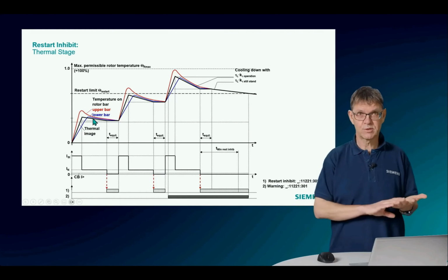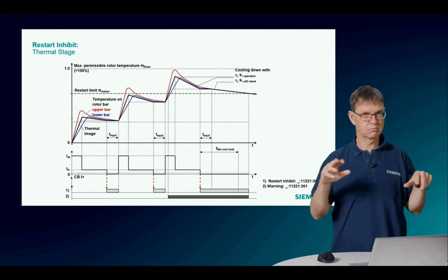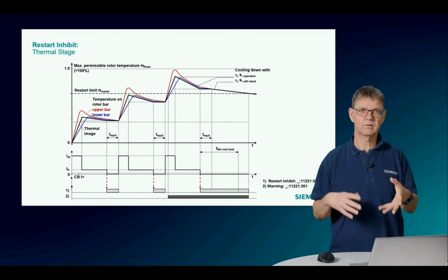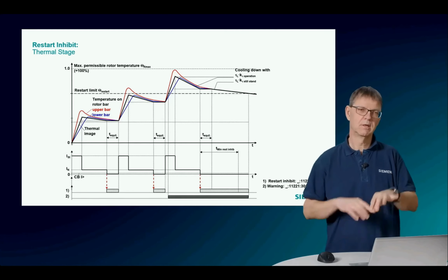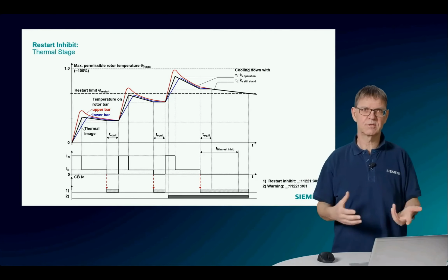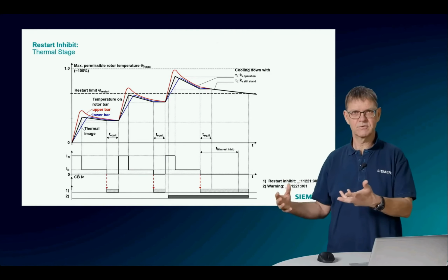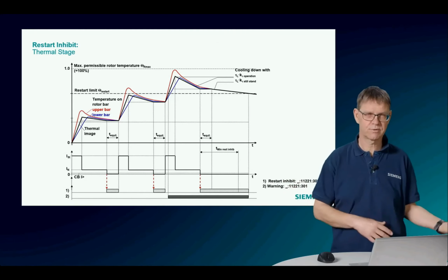And what we do with this thermal model is to make a kind of mean value based on the given data from the motor manufacturer, because the motor manufacturer already has included that consideration when he gives us the information: I can start 3 times, for example.